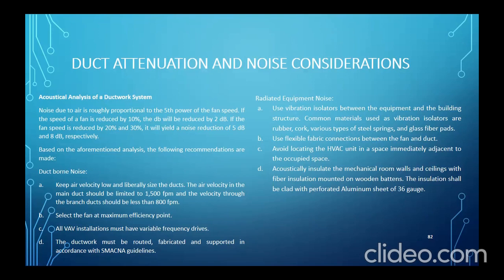Radiated equipment noise. A. Use vibration isolators between the equipment and the building structure. Common materials used as a vibration isolator are rubber, cork, various types of steel spring, and glass fiber pad. Yung mga equipment mo, huwag mo lang basta ipapatong sa sahig. Kailangan mo ng mga vibration isolator. B. Use flexible fabric connection between the fan and duct. C. Avoid locating the HVAC unit in a space immediately adjacent to the occupied space. Mga machine room mo, katabi ng opisina mo.